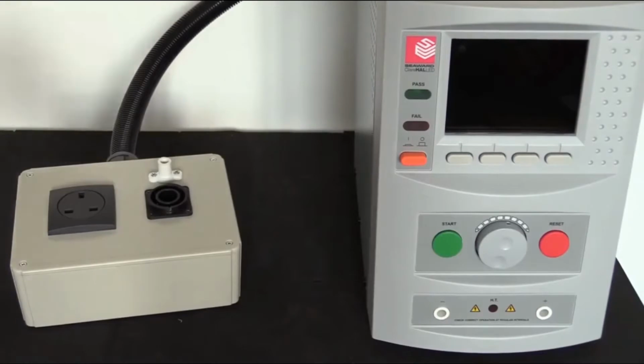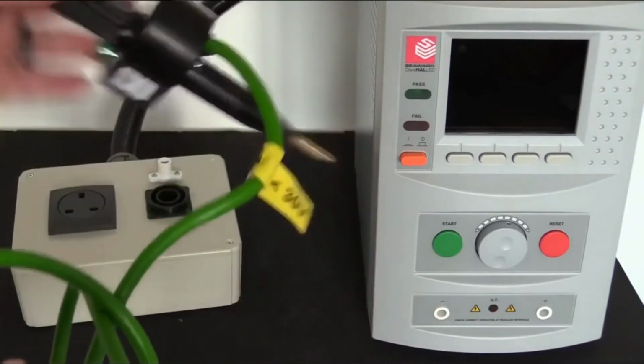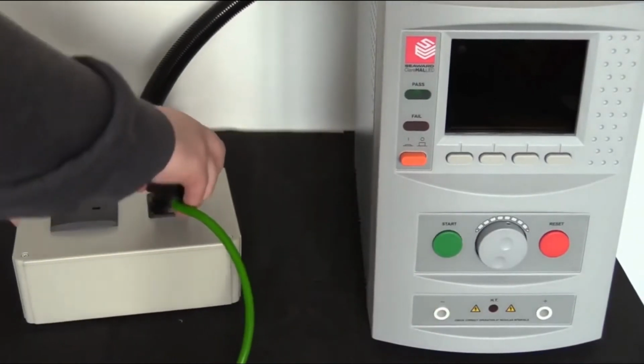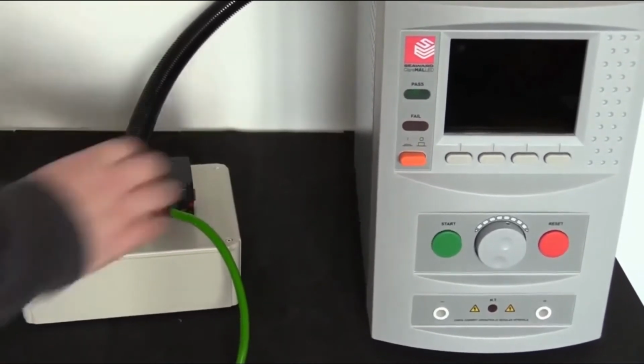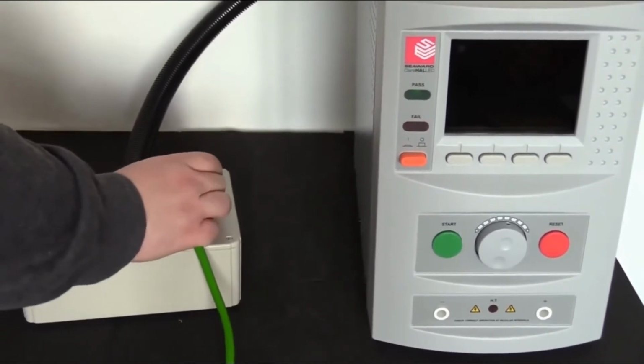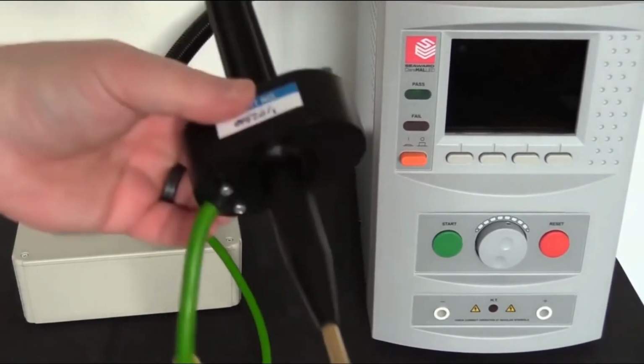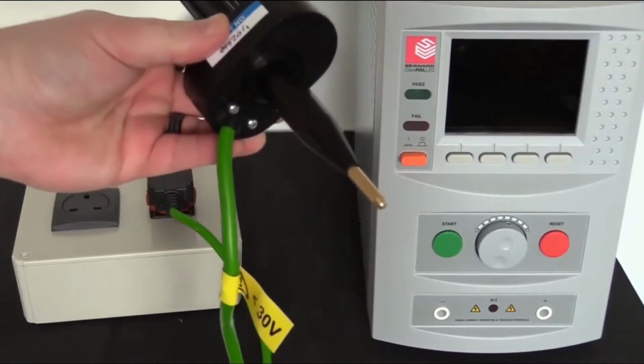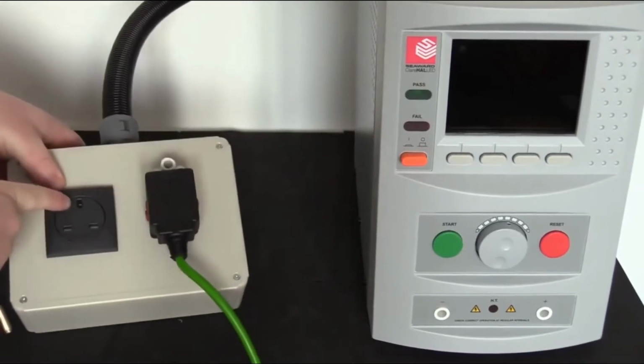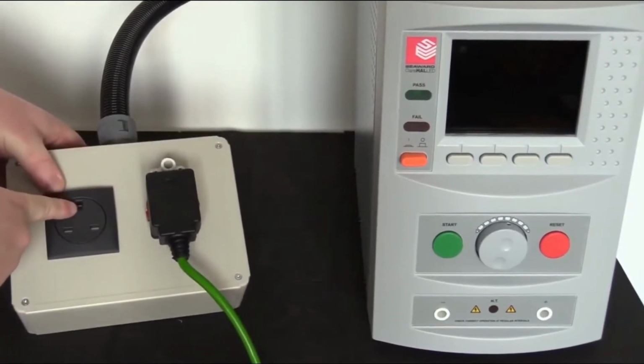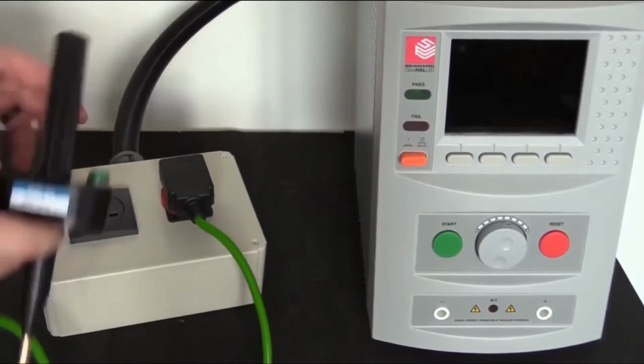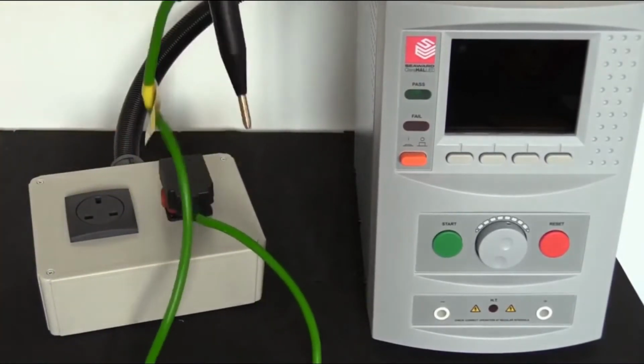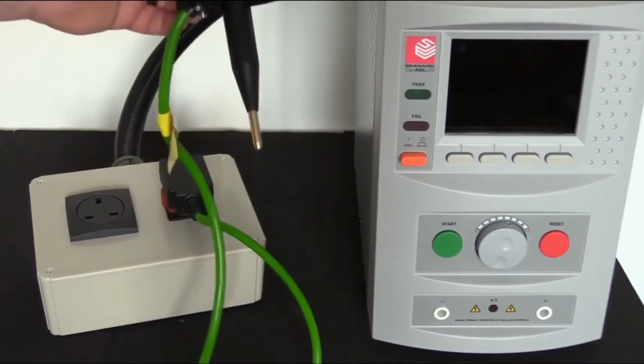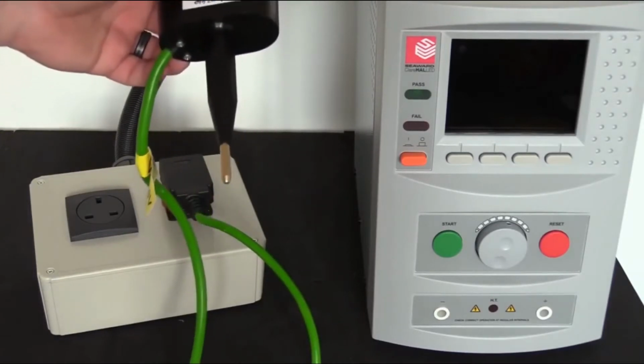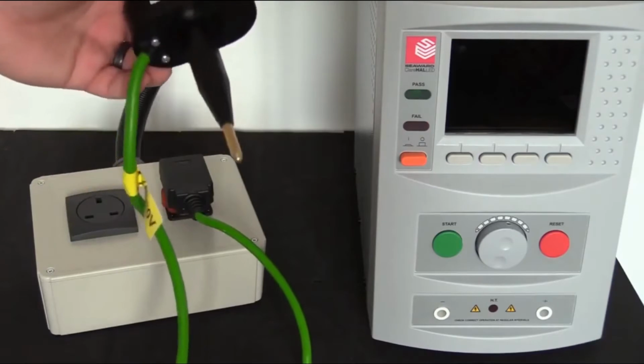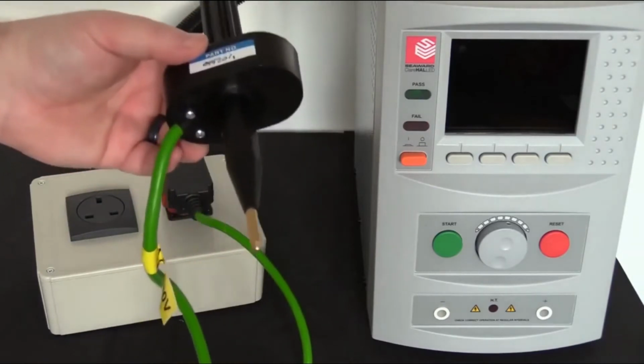We have our green cabled Earthbond probe. This is made by placing that into the connection and just twisting to lock in place. Test connections are made between the tip of the probe and the earthing point on the socket. So we would typically plug our product in, and place our probe onto the exposed metal surface of the product and use that to test for our earth continuity or Earthbond test.